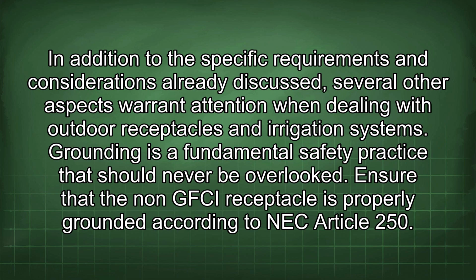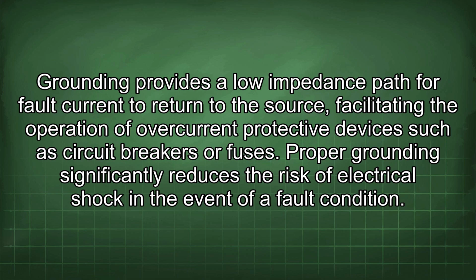and irrigation systems. Grounding is a fundamental safety practice that should never be overlooked. Ensure that the non-GFCI receptacle is properly grounded according to NEC Article 250. Grounding provides a low impedance path for fault current to return to the source, facilitating the operation of overcurrent protective devices such as circuit breakers or fuses. Proper grounding significantly reduces the risk of electrical shock in the event of a fault condition.